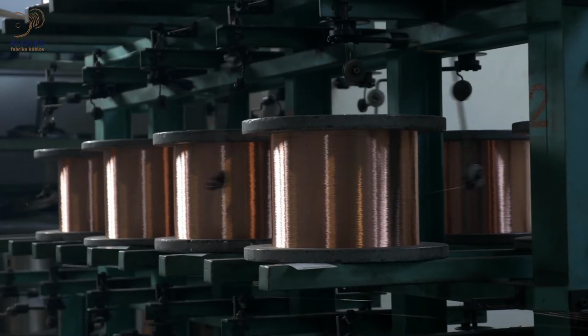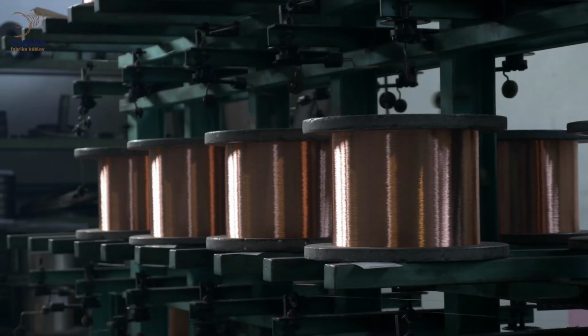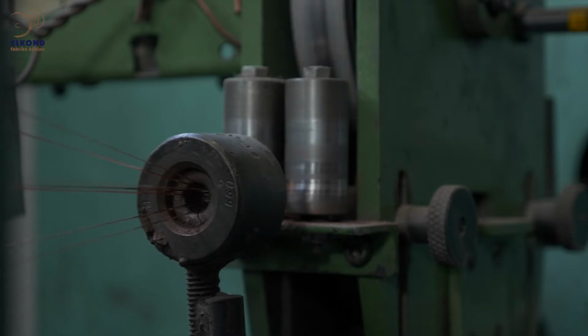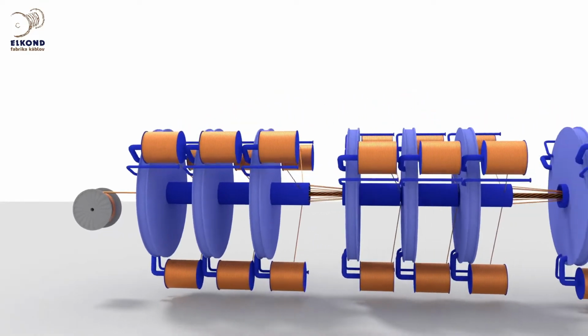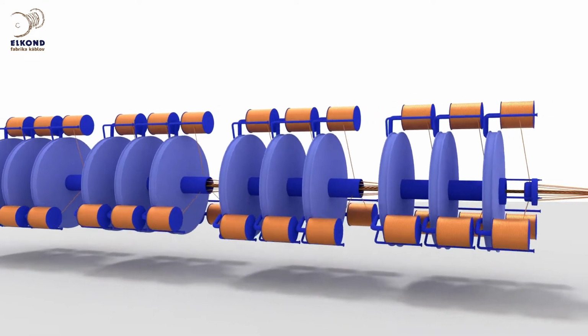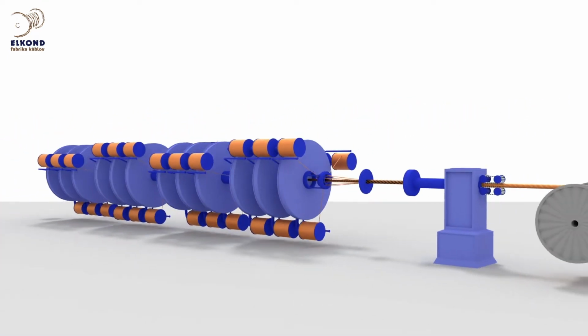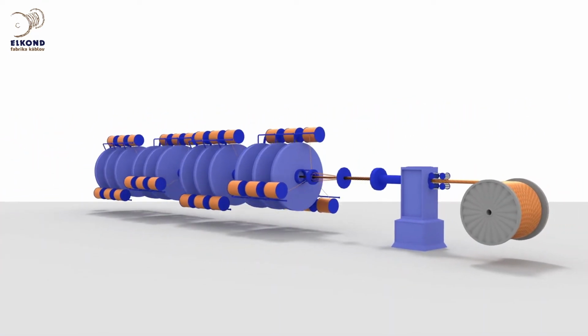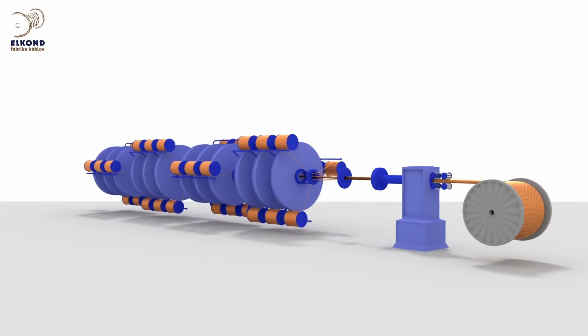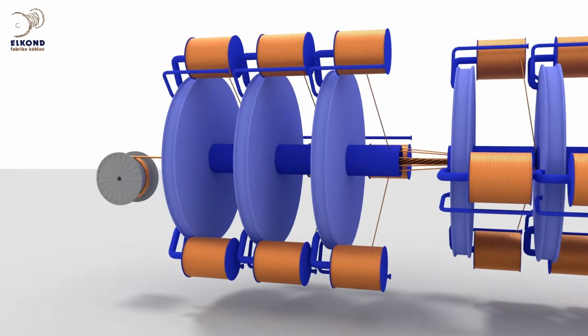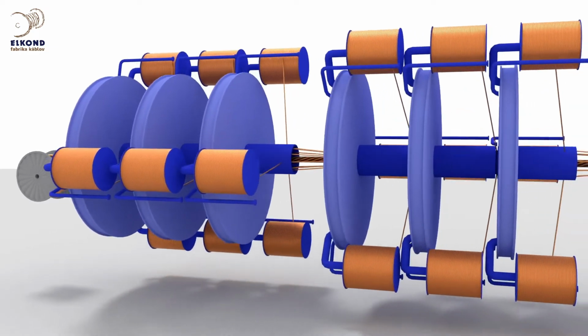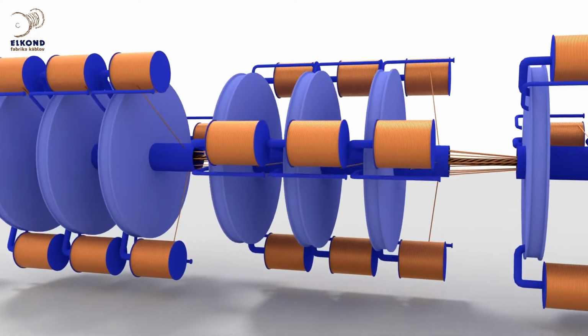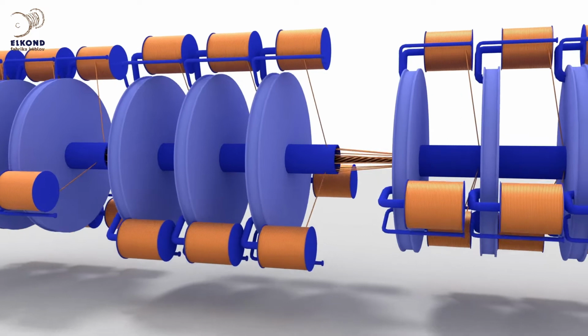In cables, 2 types of cores can be used. For fixed installation, for example into a wall, we use cables with solid wire cores. In the case of flexible cables, for example in lawnmowers, we use copper strands consisting of multiple wires. Depending on diameter and flexibility class of such rope, these are twisted into regular or irregular constructions.